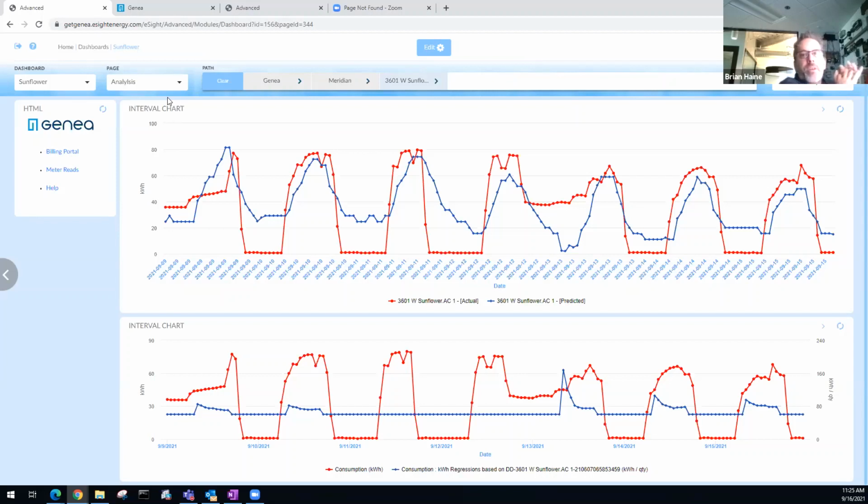And you can see, because this unit has been running off hours when it shouldn't have been, it's actually skewed the prediction a little bit and said that we should be consuming energy when in fact, because it's unoccupied, we shouldn't. This again is a historical problem with the building. But this is a good way of showing some of this data and actually looking at it and seeing where the problems are, what days are the problem.